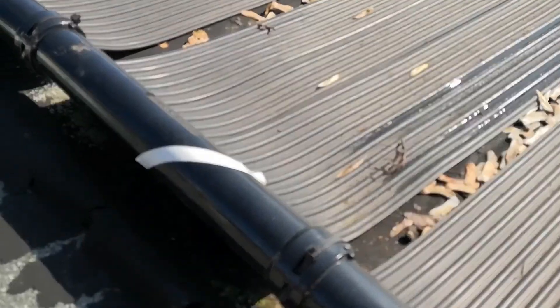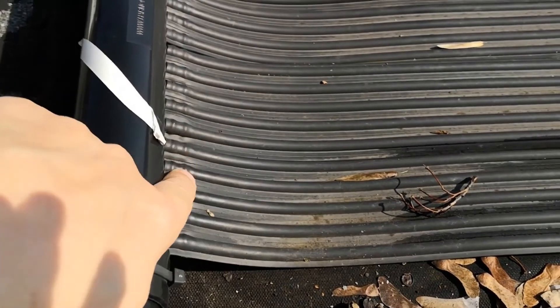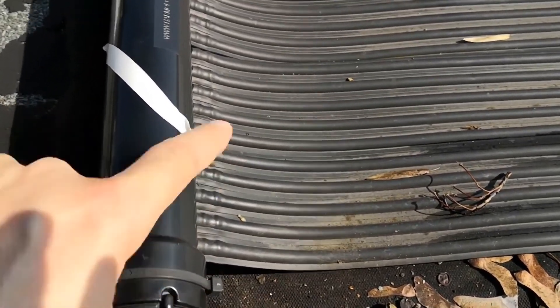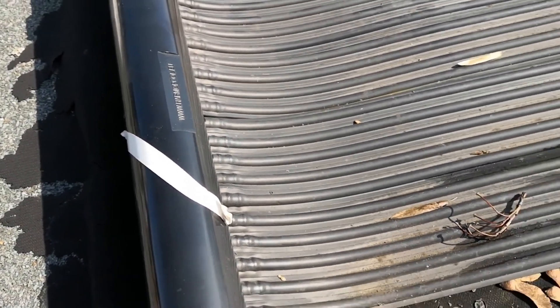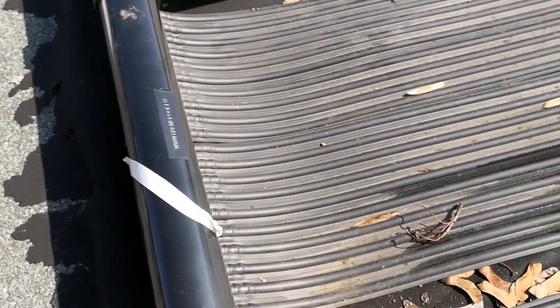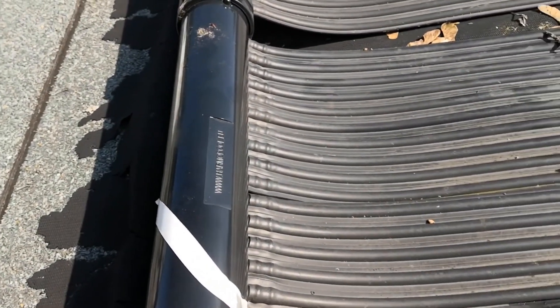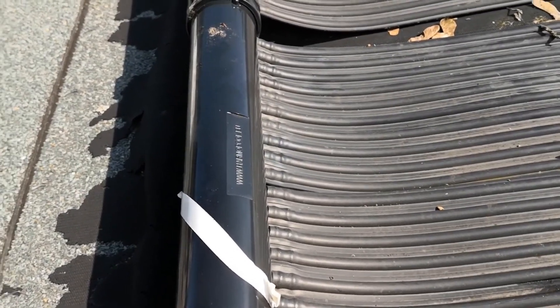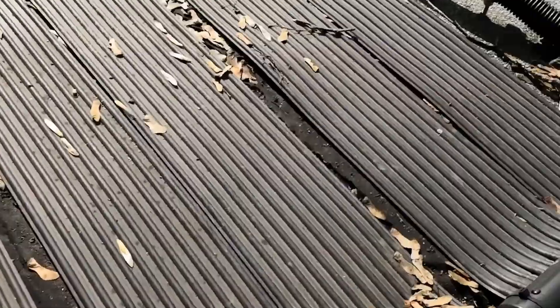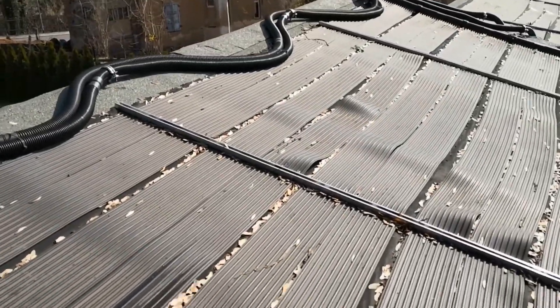You can see well here how water is standing in the mats. The mat itself will not need repairs, but the connection pieces — the hoses attached to the adapters — are currently leaking. I will completely dismantle this mat, and in my workshop, I'll try to glue or secure these connections. On five or six of the hoses, water is leaking — not just a little, but a significant waterfall. So I will completely remove this mat and replace it with a replacement mat.